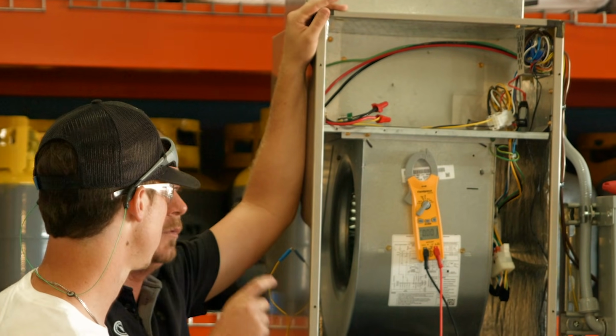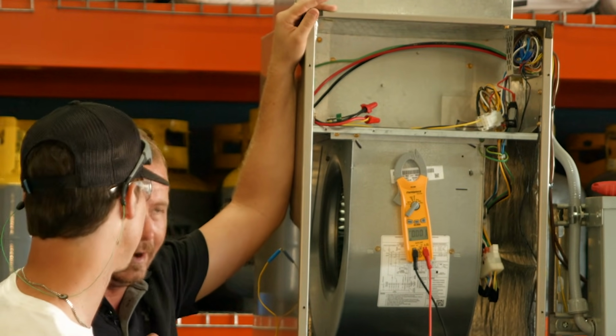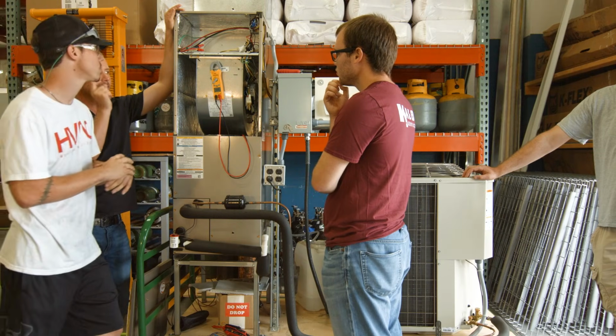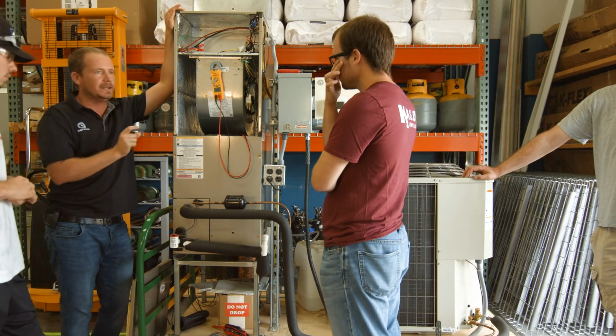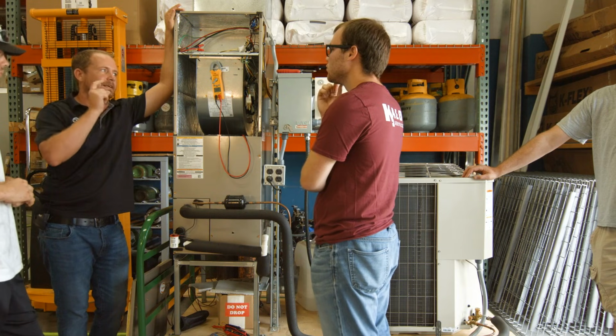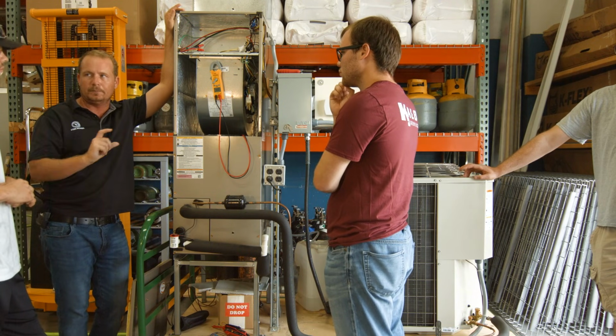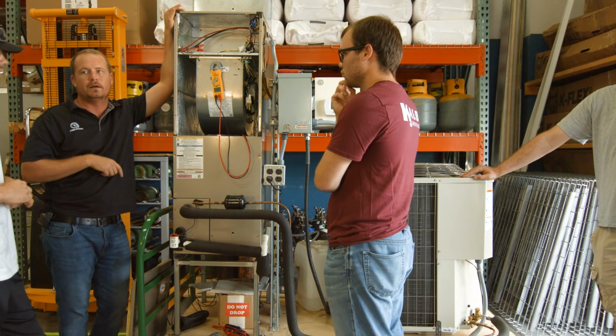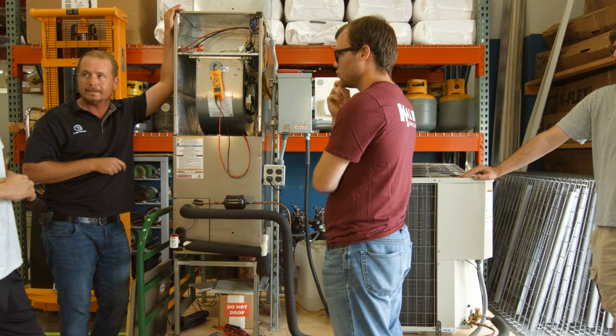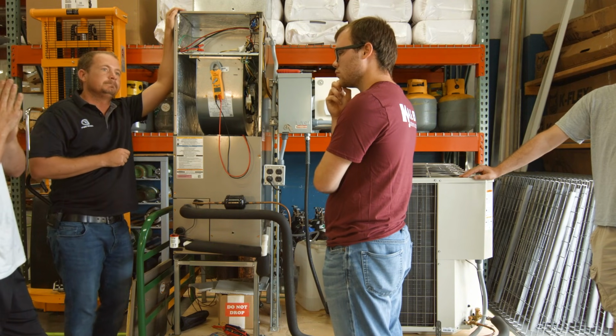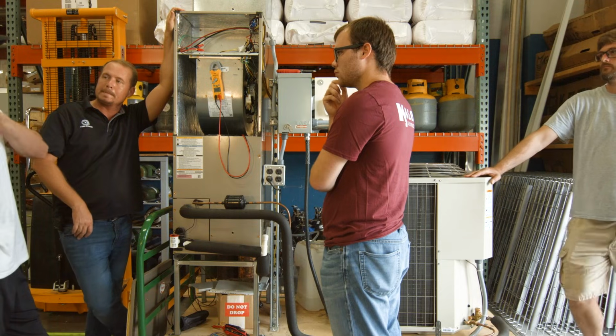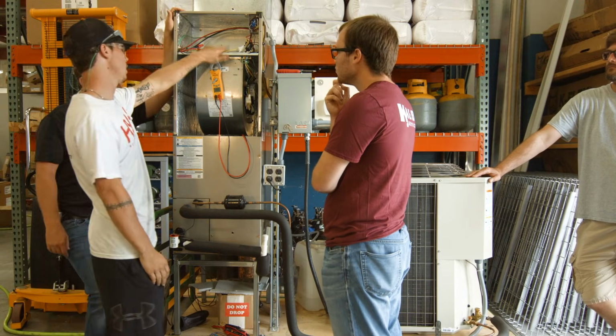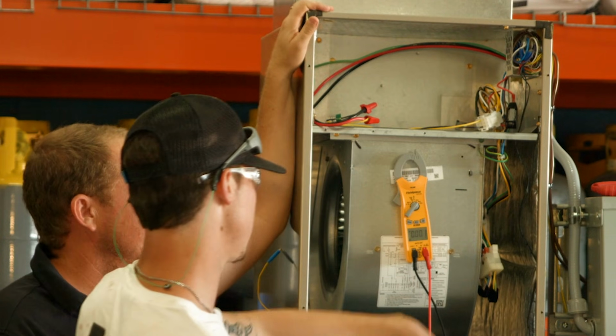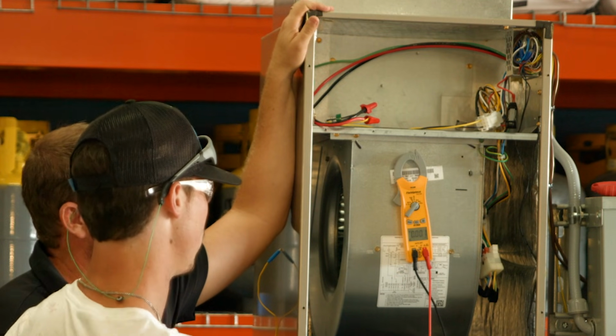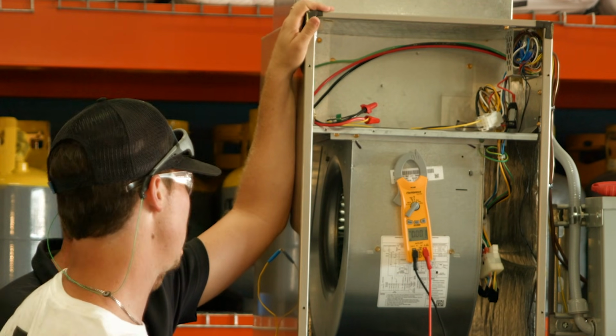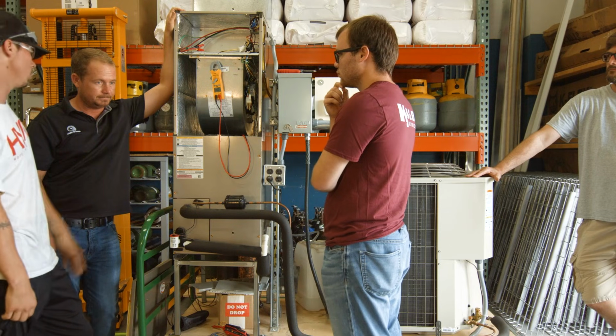So now we need to identify where the short is exactly, figure out which circuit it's in, and then which conductor it's in. We can do that a couple different ways, but I want you to approach it however you would first. Normally with this, I will unwire and separate my air handler wire going to my thermostat and my air handler wire going to my condenser, and I like to wire nut them and ohm them out.